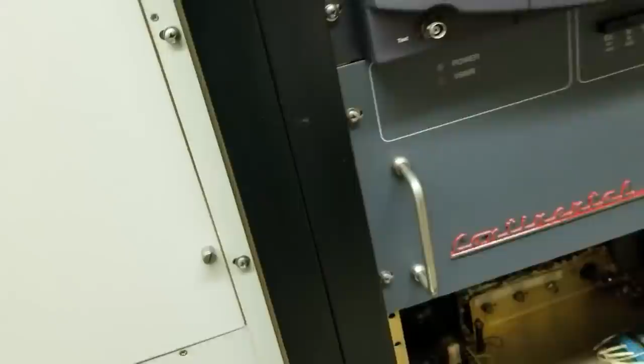This tube has got to stay cool, and there's an incredible amount of air that's pushed through that cavity with a blower underneath. And this cabinet right here is pressure interlocked. I need to get my meter leads out. When I open the door here below the tube socket, an air sensor in there will notice a pressure drop, and it will shut off the high voltage. In this case, the high voltage is not on. And it'll also shut off the filament voltage to keep from damaging the tube. And I'll quickly jerk my meter leads out of there because I'm through with that meter. As soon as I close the door, the filament voltage is back up.